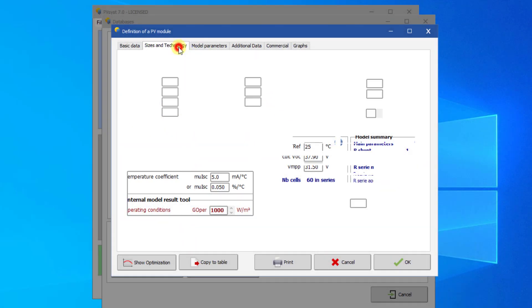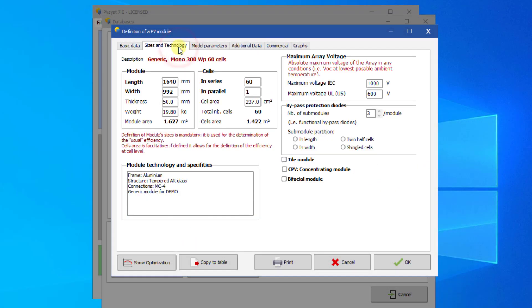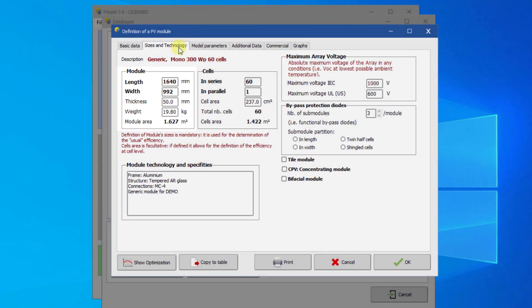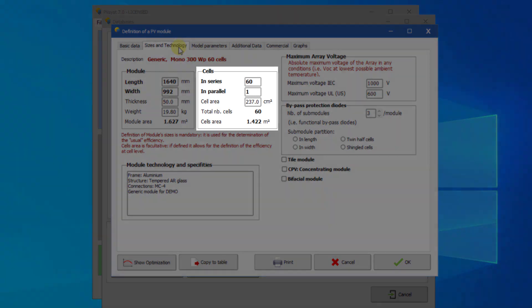Click on Sizes and Technology. It is mandatory to define the size of the module. It is also mandatory to define the number of cells in series and in parallel. Please note that this concerns how the cells are electrically connected. Typically, these are 60 or 72 cells in series and one in parallel. It does not mean the number of cells as geometrically arranged in the PV module, as often specified on the datasheets.